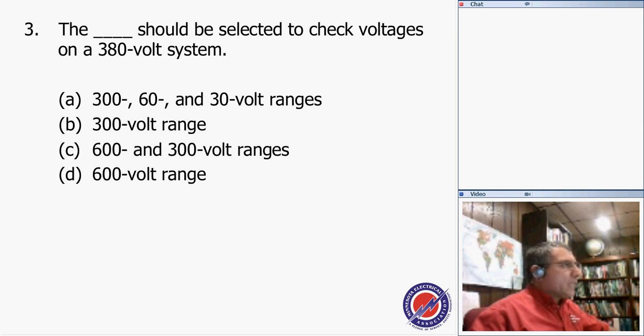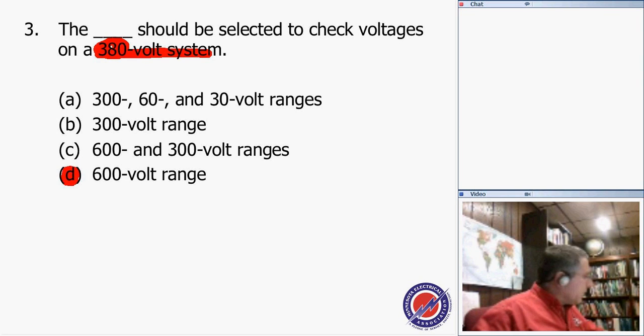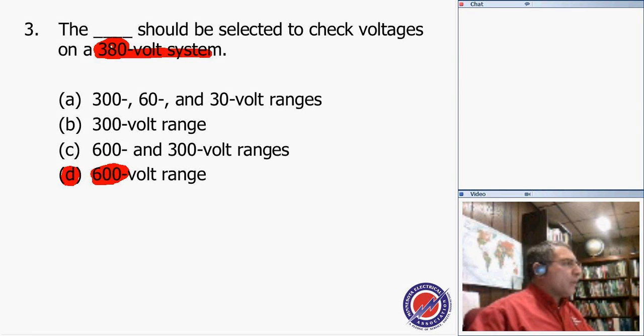Number 3: which range should be selected to check the voltage on a 480 volt system? Our answer for this one, number 3, is D, 600 volts. When you have a voltmeter, guys, the voltmeter must have the same voltage or higher, the same voltage or higher.